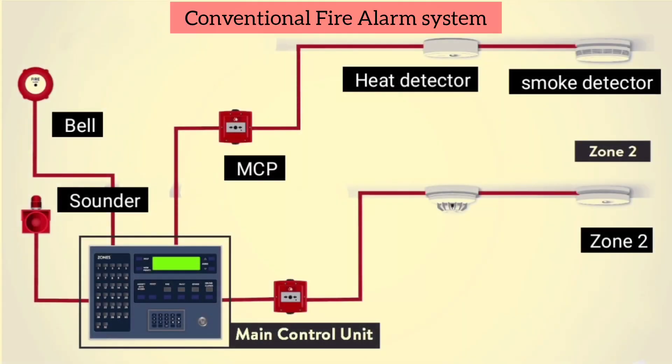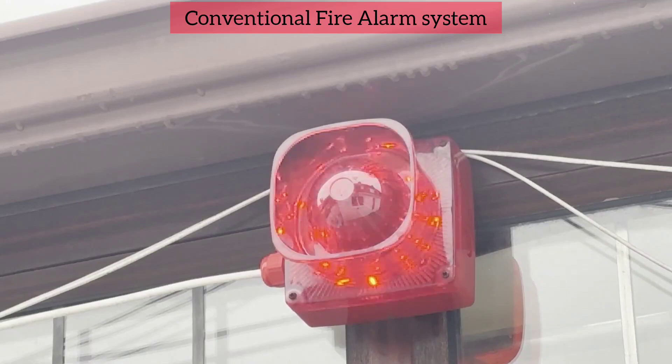Conventional fire alarm system. In a conventional fire alarm system, detectors and call points are wired in zone circuits using class B wiring, and a maximum of 25 to 30 devices can be wired on each zone. Zones simplify locating the cause of a fire alarm. The control panel is wired to a minimum of two sounder circuits, which could contain bells, electronic sounders or other audible fire alarm devices. It is these devices which sound the alarm when triggered.